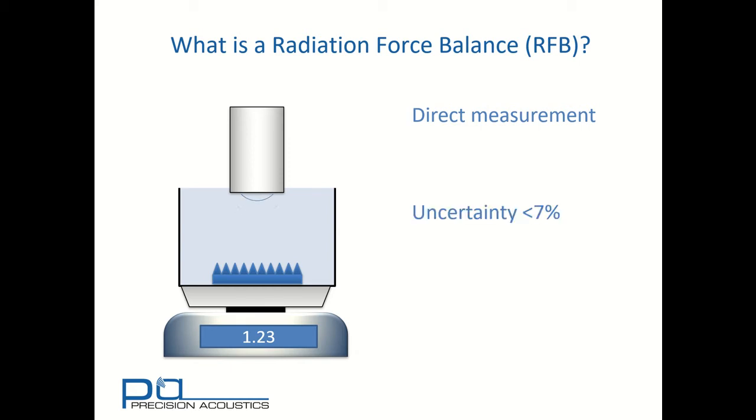This allows us to achieve measurement uncertainties typically less than 7%. And radiation force balances are sufficiently important in the measurement of ultrasonic power that there is an IEC standard dedicated to their implementation. This is IEC 61161.